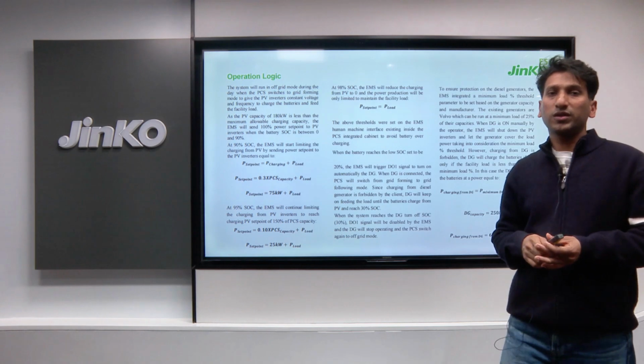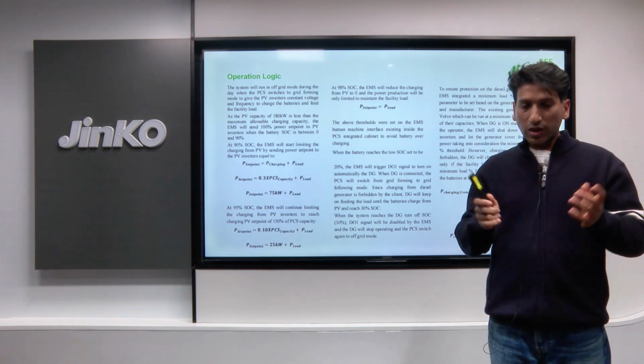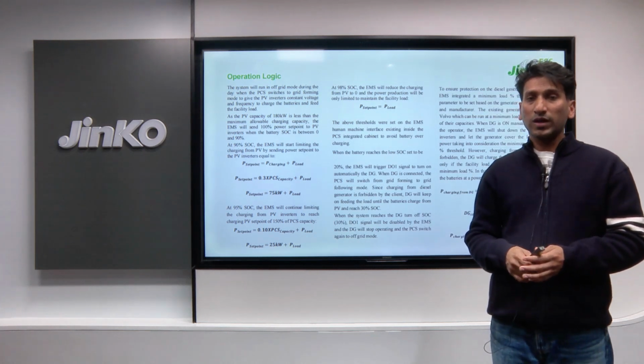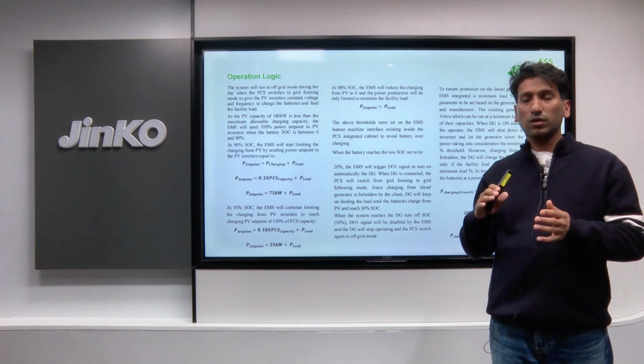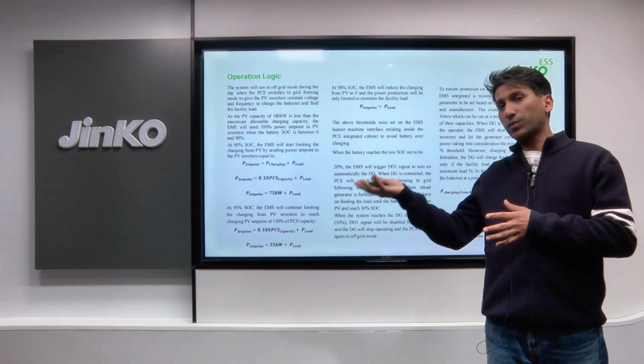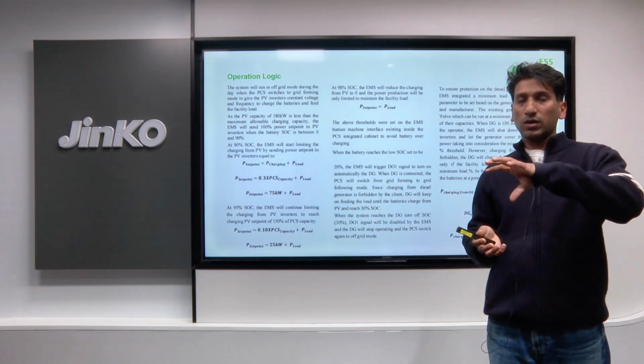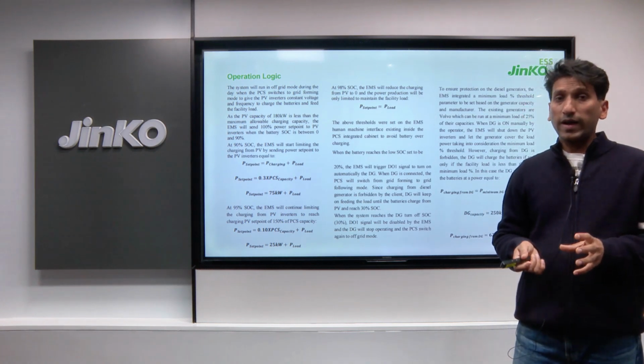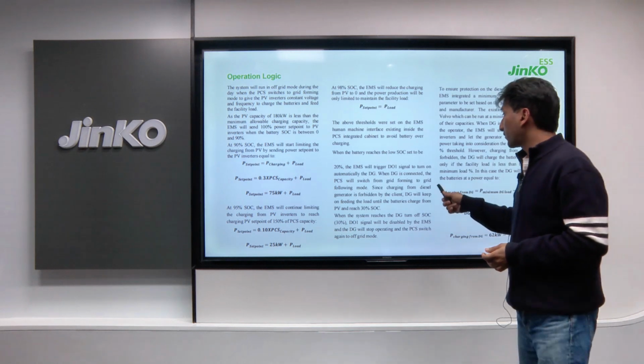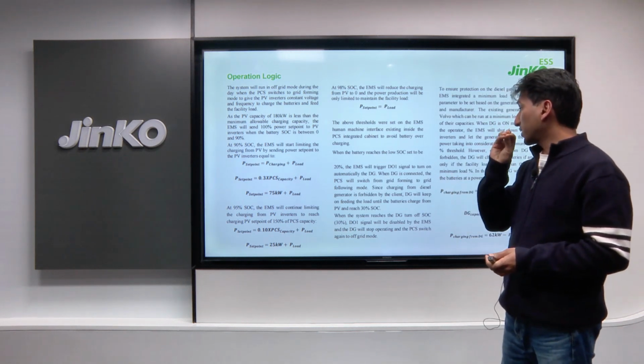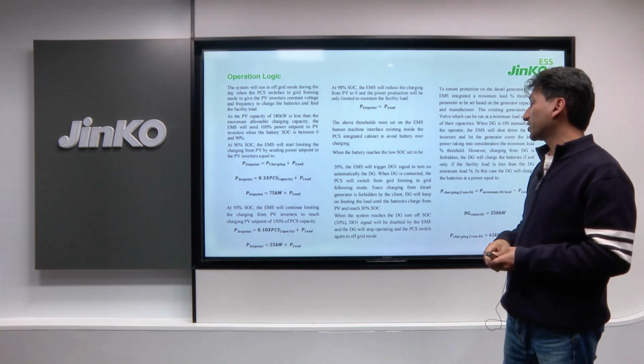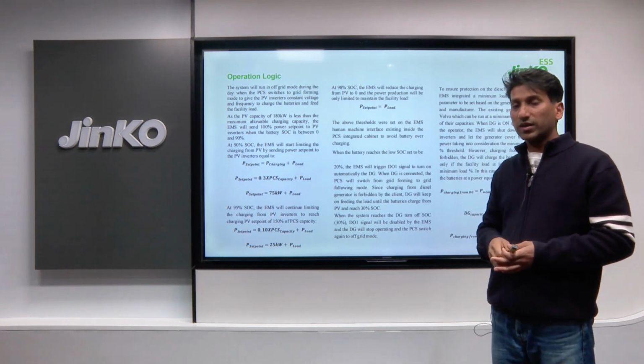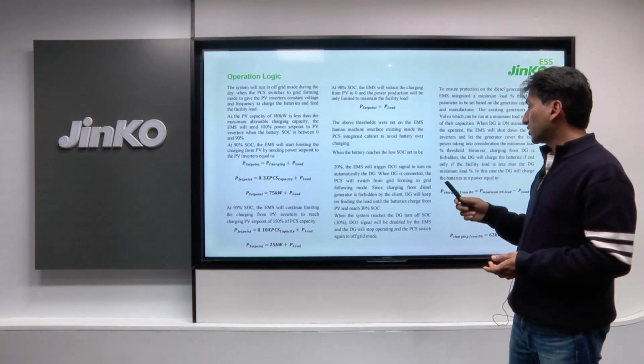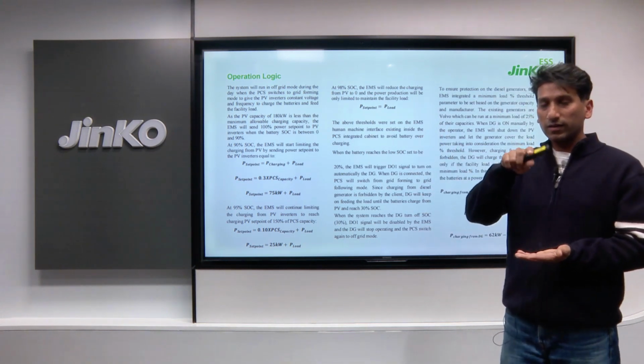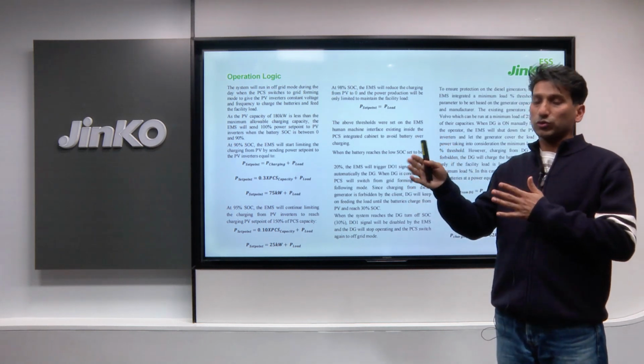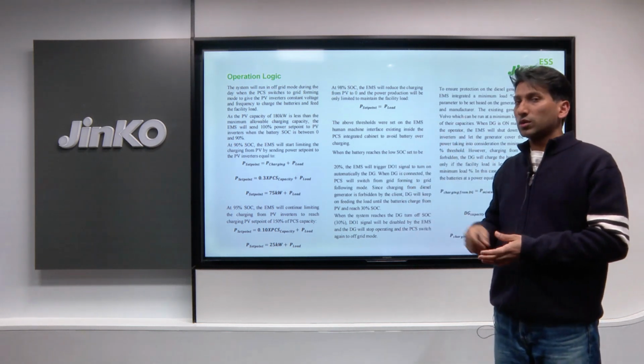In this whole system scenario, where the DG will play its part, the battery SOC keeps going down, supply keeps supplying to the load, and PV is also supplying to the load. But if the battery SOC goes less than 20%, at that point the DO signal from the EMS, the dry contact signal, will send a command to the diesel generator, and the diesel generator will start working and charge the batteries. When the SOC reaches 30%, the diesel generator will stop again, and then the system keeps supplying power to the load. When the SOC goes below 20%, it starts again and keeps supplying to the load.